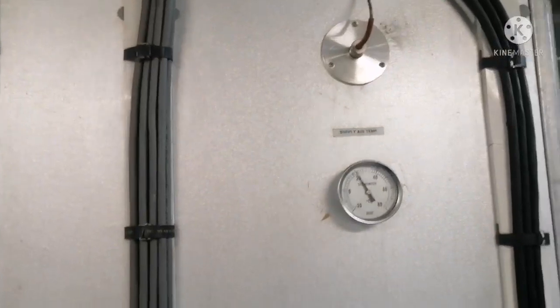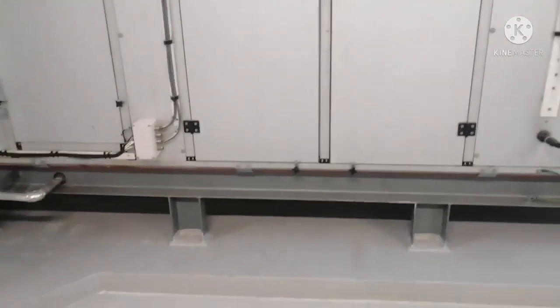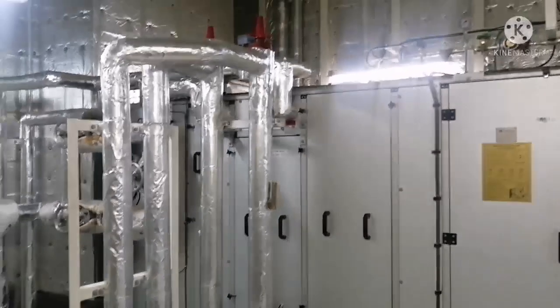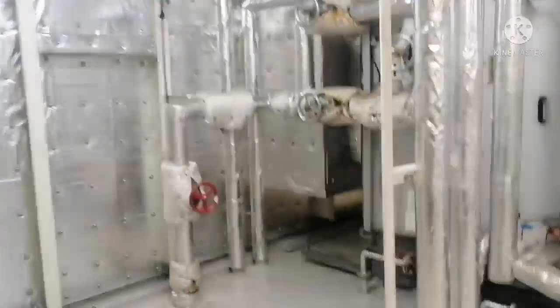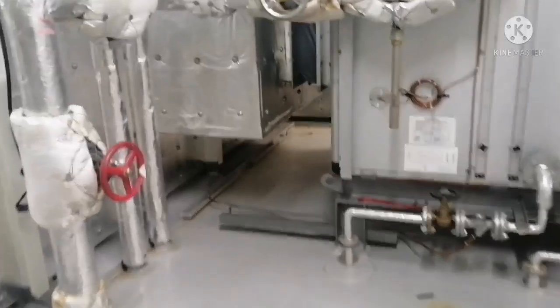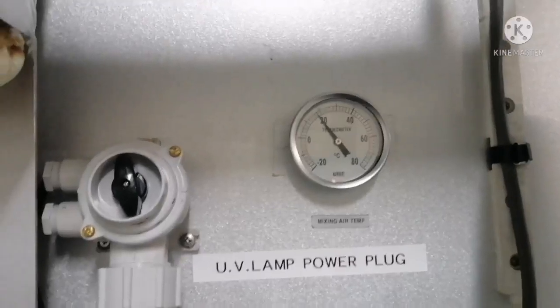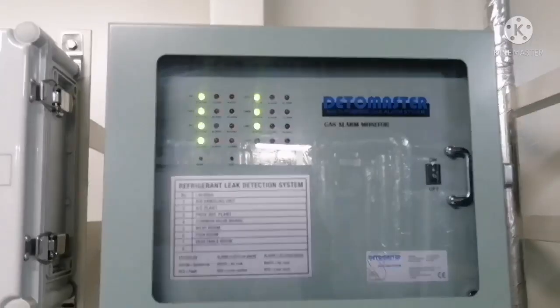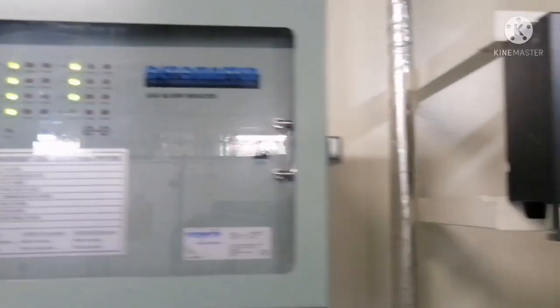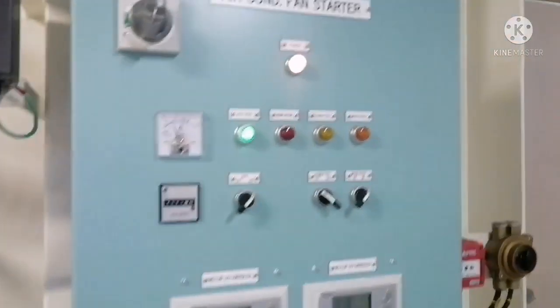so now we go to the air handling unit. So this is your air handling unit room. You have to see the temperature. This indicates your accommodation inlet temperature. Again check for any leakages. Usually here you can find the drain getting choked and water starting to overflow, so that you have to check. Here you can see it is very clean. And okay, you can check for any gas leakages. All are in green zone, so no problem, everything is fine.